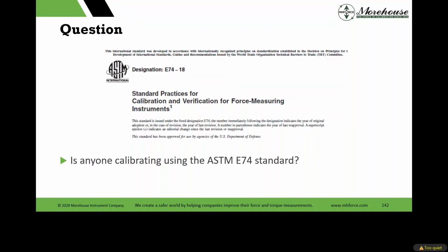How important are load cell simulators? Yeah, so when we were talking about the meters, I'm going to hold those questions, Luke and Tim, a little bit. But yeah, if you want to establish that traceability chain, I have some posts on how you calibrate meters and the simulators and how to do that. And then there's whether it's in accordance with E74, or we have an ultra cheap, pretty good simulator that could be used if you just want to play around with some stuff. You can certainly get traceability with it, but if you want to calibrate to the E74 guidelines, it's not good enough for that because it doesn't have the steps. It's like a $500 simulator compared to one that's $4,000.